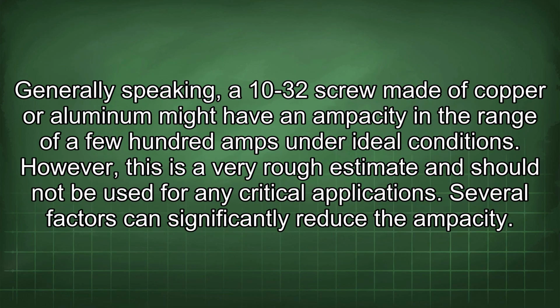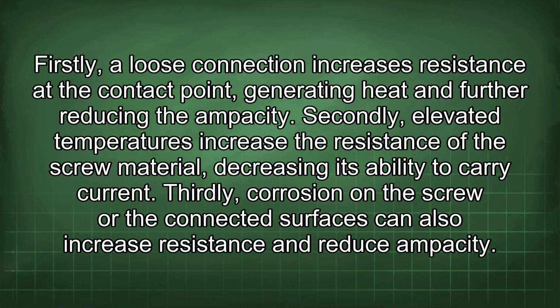Generally speaking, a 10-32 screw made of copper or aluminum might have an ampacity in the range of a few hundred amps under ideal conditions. However, this is a very rough estimate and should not be used for any critical applications. Several factors can significantly reduce the ampacity. Firstly, a loose connection increases resistance at the contact point, generating heat and further reducing the ampacity. Secondly, elevated temperatures increase the resistance of the screw material, decreasing its ability to carry current.